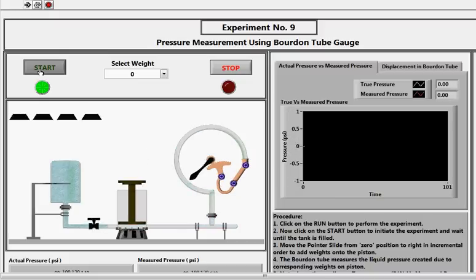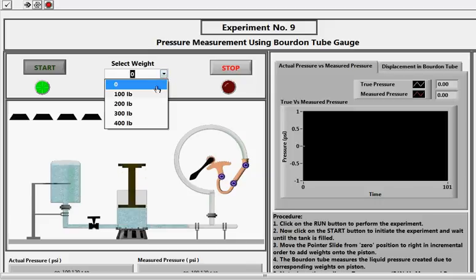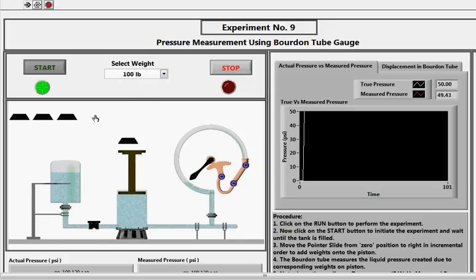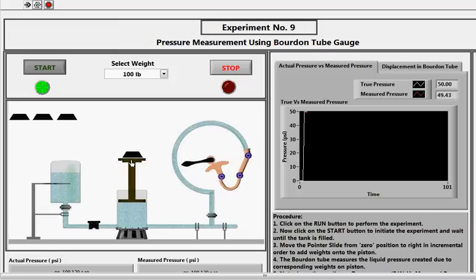Select the weight from the drop down menu. Suppose you select the 100 lb weight, then that 100 lb weight will come and rest on the piston. Due to that, pressure will be applied and the curve of the Bourdon tube expands and the needle connected to the curve moves and will indicate the pressure applied.